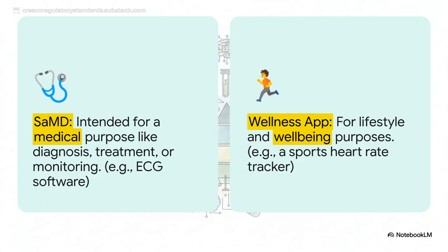You know, this is the exact spot where most people get tangled up. So let's make this crystal clear. An app that just tracks your heart rate while you're on a run, that's a wellness app. But software that takes that exact same heart rate data, runs an analysis, and then alerts you to a potential atrial fibrillation. Now that is SaMD. The intended purpose is the bright, uncrossable line in the sand.